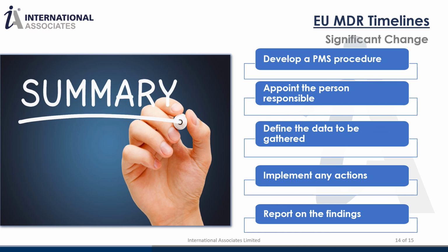One of the most difficult parts is defining which data is important for the medical device in question. Keep in mind that the range of data to be monitored should be in direct proportion to the risk associated with the device, based on its intended use. An effectively set up PMS system indicates potential shortcomings in the design or production of your device and defines how you will action them.